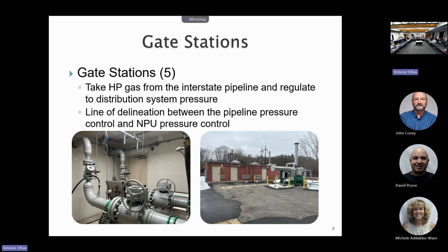We drop it down into our serviceable pressures to send out to our district regulation stations. That's the Salem gate station right there. The facility in front of it with the green framing is a heater, a bath heater, so we can heat that natural gas up. We want to keep the regulators from freezing, so we try to maintain a constant temperature, that 34 to 35 degree range on the bottom end, to make sure we don't have any freezing inside our regulators. That's actually inside the station itself.